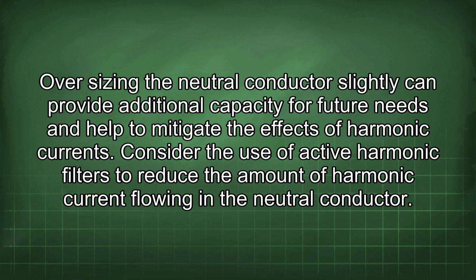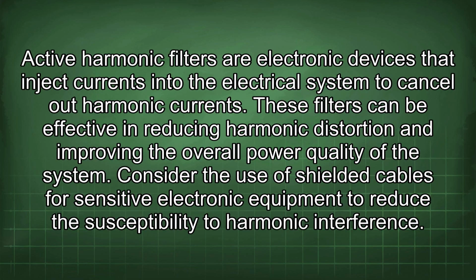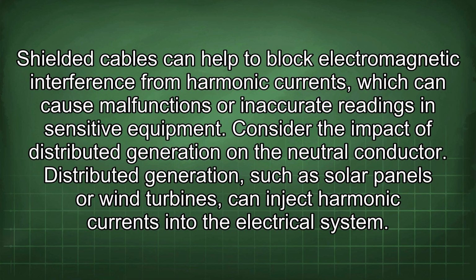Consider the use of active harmonic filters to reduce the amount of harmonic current flowing in the neutral conductor. Active harmonic filters are electronic devices that inject currents into the electrical system to cancel out harmonic currents. These filters can be effective in reducing harmonic distortion and improving the overall power quality of the system. Consider the use of shielded cables for sensitive electronic equipment to reduce the susceptibility to harmonic interference. Shielded cables can help to block electromagnetic interference from harmonic currents, which can cause malfunctions or inaccurate readings in sensitive equipment.